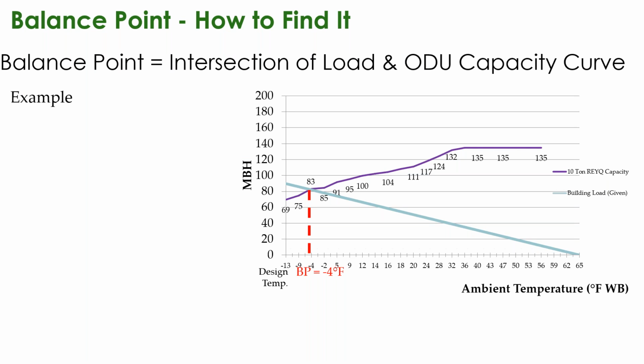Now, this is an average 10-ton unit. Given your load, no load at 65 degrees, and your design load, in this example, at minus 13, you plot the outdoor capacity of that, and the lines intersect at about minus 4 degrees outside. This would be your balance point, and we'll talk a little bit more about this specific to both supplemental and what we call alternate heat.